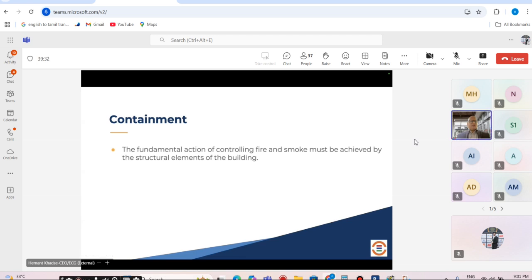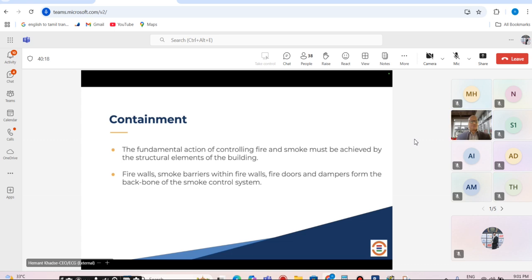So going forward, containment is the most common strategy applied, especially in various high-rise buildings. It could be commercial, residential, or hotel, where you are trying to control the fire and smoke to that specific area structurally. So it is important that we validate that along with the architects, with the fire rating that is expected or required by the codes and standards. It could be fire walls, fire doors, dampers, and it covers both horizontal and vertical smoke propagation.